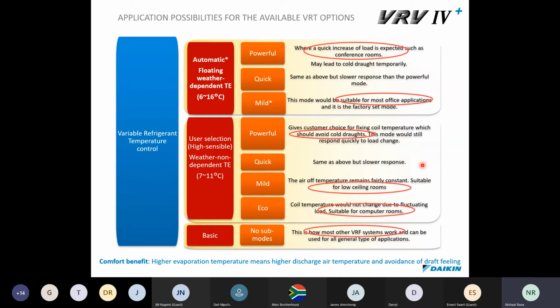Also, think about a diffuser. Let's say the architect hit the stuff up, or you put wall grills at maybe 2 meters above the finished floor level, and now the person at the desk is starting to feel uncomfortable. And let's say everyone's feeling uncomfortable. You don't have to have the VRV discharging at an evaporation temperature of 6 degrees. You can do it at 9 degrees. Trust me, 3 degrees makes a big difference in terms of comfort. You can try it. That's why people are comfortable at 23 degrees and are uncomfortable or start getting twitches or a bit jumpy at 20 degrees.